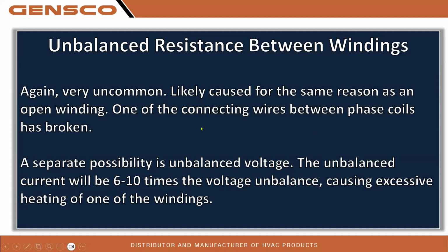This is where the balanced voltage test comes in, where we want to see all three phases feeding the compressor pretty close to the same number. We would like to see like 152, 151, 150. That's pretty balanced. But if we see 152, 151, 137, not balanced. And of course, if we see something like 152, 151, and 21, it's not going to run. That's going to single phase the motor and it won't start.